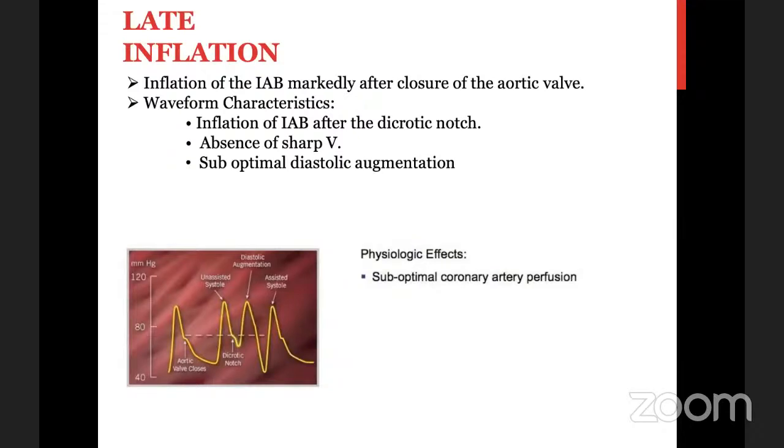The other issue is late inflation, which is inflation of the intra-aortic balloon pump markedly after closure of the aortic valve. The characteristics are inflation of the balloon after the dicrotic notch, absence of the sharp V wave, suboptimal diastolic augmentation, and suboptimal coronary artery perfusion.